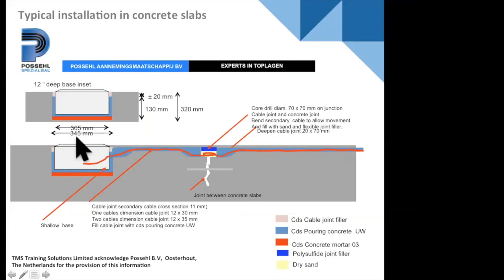Let's say this is a touchdown zone or a taxiway centre line or a runway centre line light, etc., and our transformer is off to the side of the pavement. We've got to get the secondary cabling, the secondary circuit, out to the light fixture across an expansion joint. Well, it's no good just putting the cable straight across, because as the surface moves with temperature changes, it would break the cable. So there are different demands, and this picture is taken, and here we acknowledge Possehl, the Netherlands.